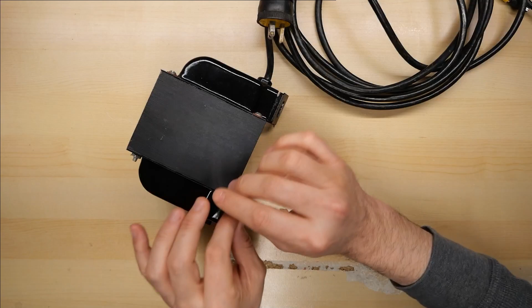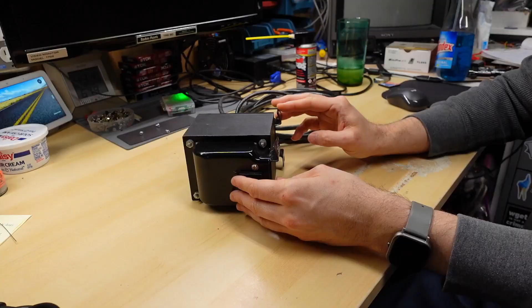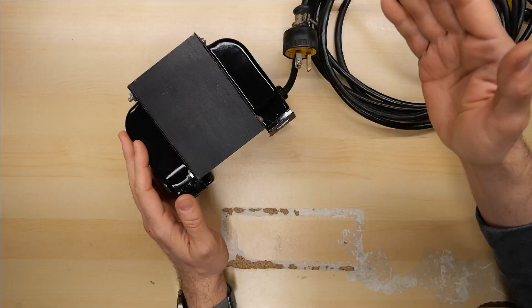With a transformer like this one, the special thing is the primary side windings, hooked up to the mains, and the secondary side windings, which connect to a regular mains plug right here, have the same number of turns. That means the voltage coming in through this mains cable, 120 volts, will be the same as what comes out. But they are electrically isolated from each other because of the way a transformer works.